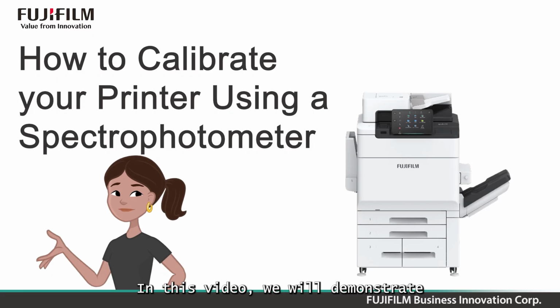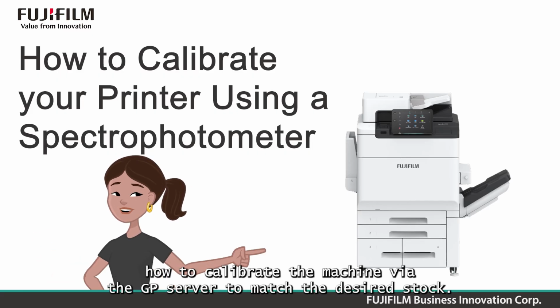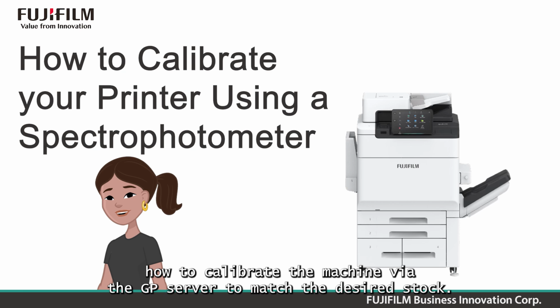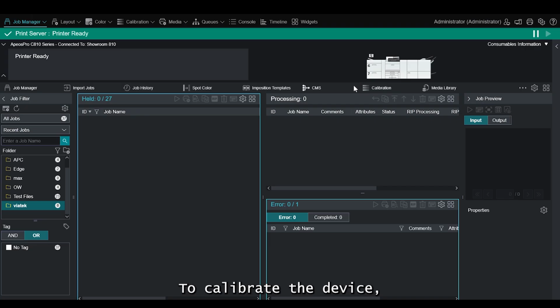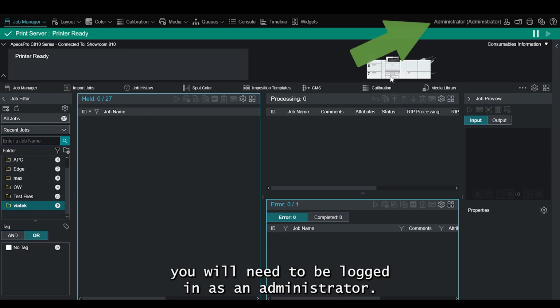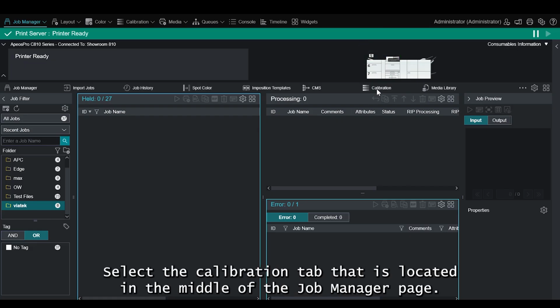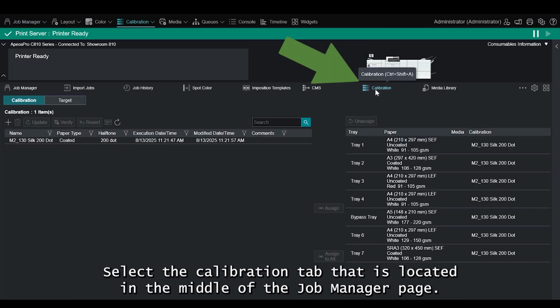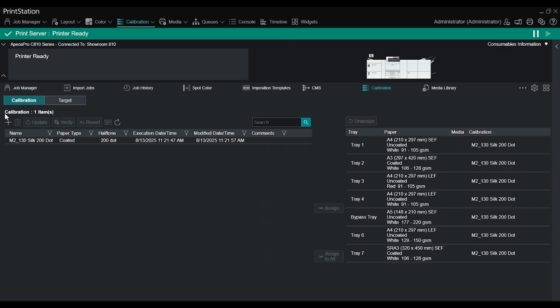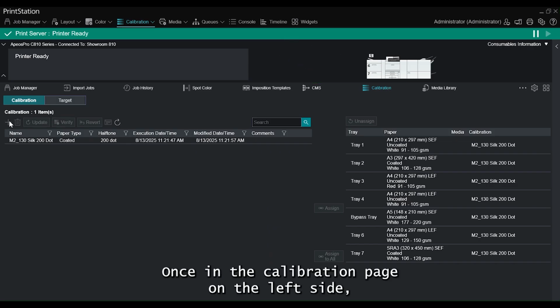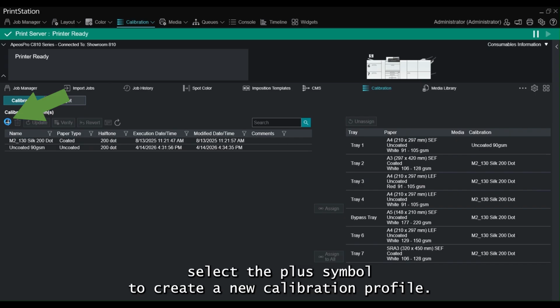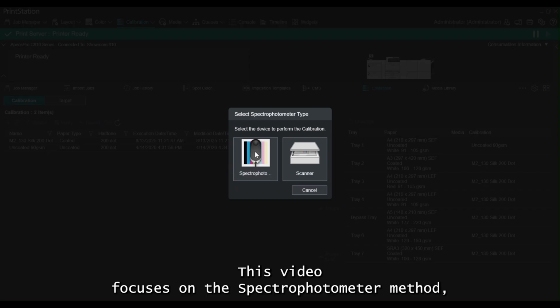In this video, we will demonstrate how to calibrate the machine via the GP server to match the desired stock using a spectrophotometer. To calibrate the device, you will need to be logged in as an administrator. Select the Calibration tab that is located in the middle of the Job Manager page. Once in the Calibration page, on the left side, select the plus symbol to create a new calibration profile. You will be prompted to select between two devices to perform the calibration. This video focuses on the spectrophotometer method, so we will select this option.